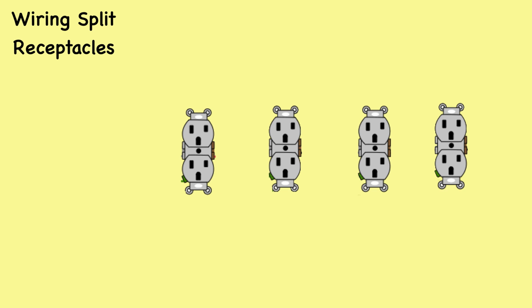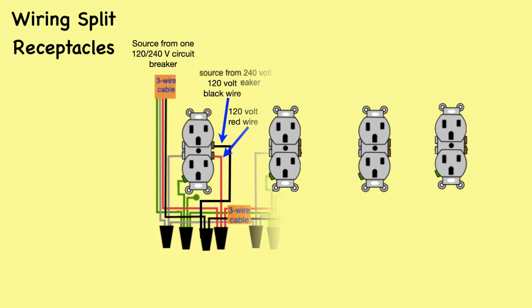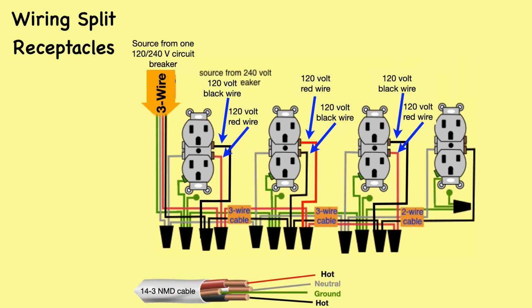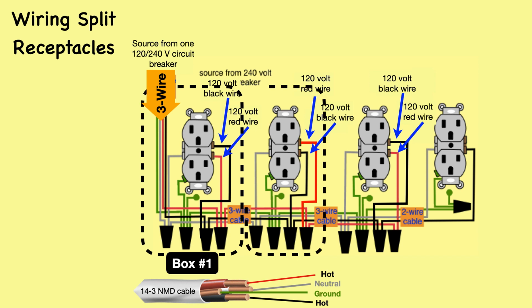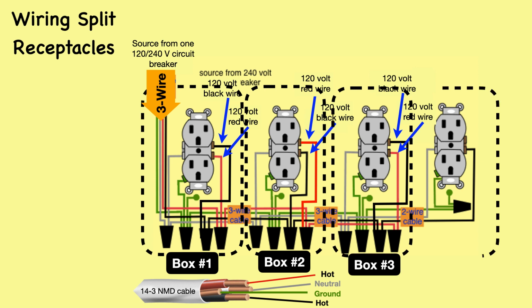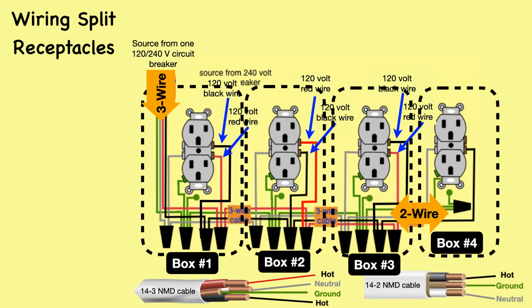As its name implies, a split receptacle is just a plug which is essentially split in two with a separate circuit supplying power to the upper portion and lower portion of the plug in the outlet. Here, a 3-wire cable is run from a double pole circuit breaker providing an independent 120 volts to 3 of the receptacles. The dotted lines around each receptacle represent the metal box containing each receptacle. 14-3 and 14-2 NMD cable connects these metal boxes as shown.